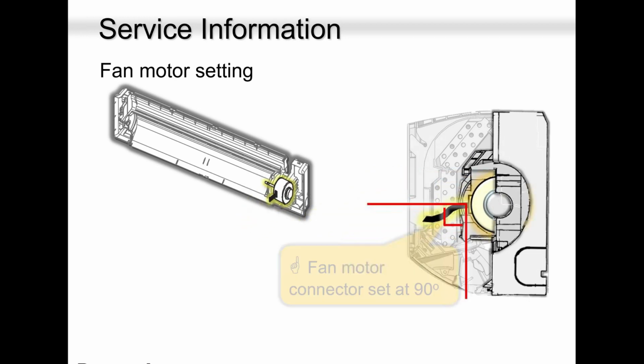Slide in the motor, put back the blower wheel, tighten the screw, make sure the wheel is not wobbly. Make sure the bushing on the left hand side has gone in nicely into the blower wheel shaft. If you have no issues, run the unit in fan only. Make sure it's not shaky. Then put everything back together.